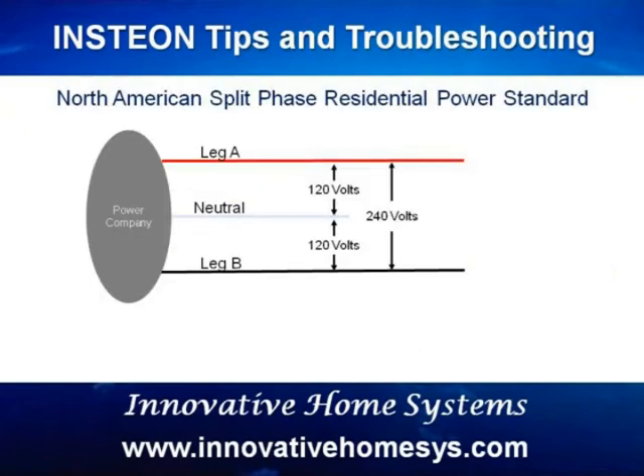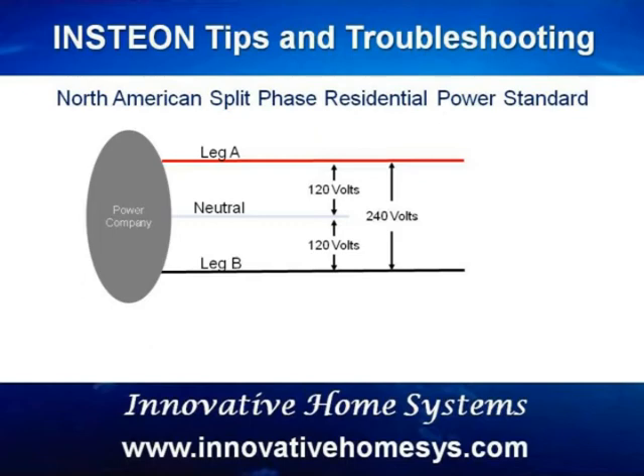The commercial power standard commonly used in North American residences and light commercial applications can be thought of as two separate 120-volt power sources that, when added together, produce the 240 volts used for heavy duty applications like electric heating, air conditioning, electric ranges, and clothes dryers. The key words here are two separate sources. While in reality they are connected in the power company transformer on your block, the two sources effectively isolate the Insteon signals from one source or leg to the other. In other words, an outlet connected to leg A entering your home system may not provide a suitable path for Insteon signals to travel to an outlet wired to leg B. The result is an Insteon device that works when plugged into some outlets but not others.